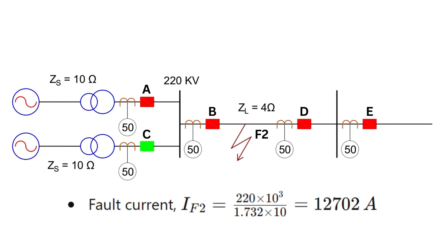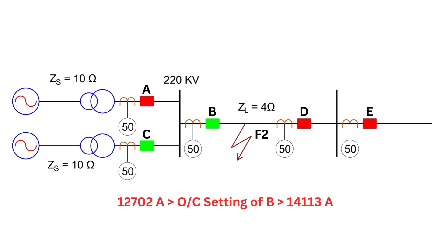Therefore, for the protection of the transmission line, the setting of relay at breaker B shall be kept less than 12,702 amperes to trip immediately. But for the earlier case, we saw that the overcurrent setting of relay at breaker B should be more than 14,113 amperes to not trip for through fault, which is impractical.